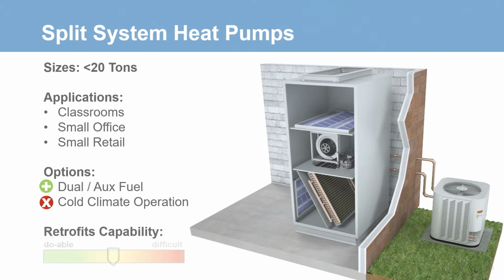These systems typically lend themselves well for electrification retrofits. The outside unit is typically in a location that is easily accessible, and new heat pump equipment will have a similar footprint. For the most part, owners and designers replace the line set, refrigerant specialties, and coil. Also worth noting, for any heat pump retrofit, the electrical feed supplying the heat pump should be checked to make sure it can handle the heat pump duty.